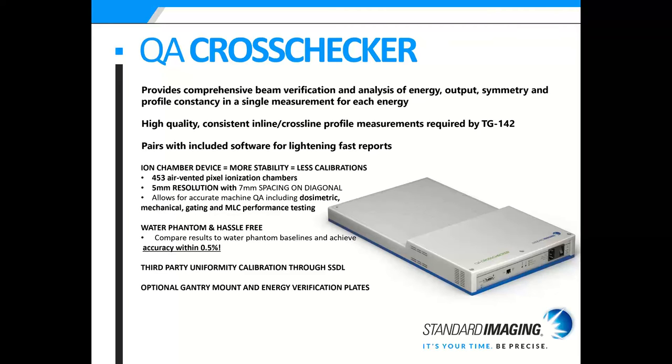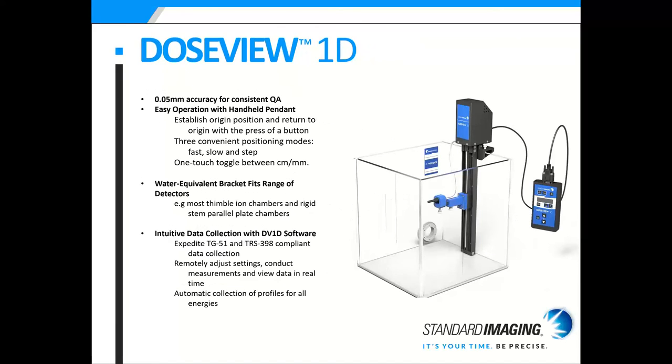There is a third-party uniformity calibration for SSDL and it comes with an optional gantry mount and energy verification plates. The DoseView 1D is our 1D tank system with 0.05 millimeter accuracy for consistent QA. It has easy operation with a handheld pendant — you can establish the origin position and return to it with the press of a button. There are convenient modes: fast, slow, and step, with one-touch toggle between centimeters and millimeters. The water equivalent bracket fits a range of detectors, and its software allows you to expedite TG-51 and TRS-398 compliant data collection, remotely adjust settings, conduct measurements, and view data in real time.